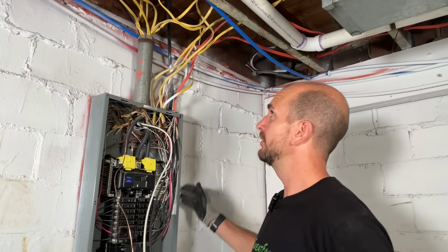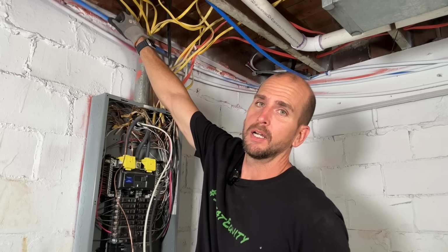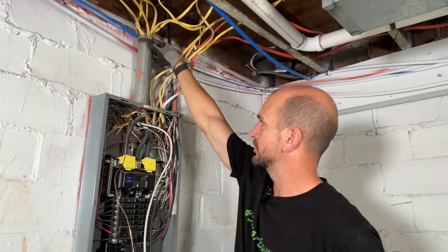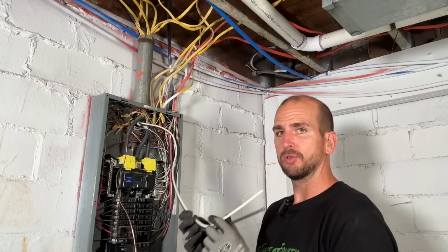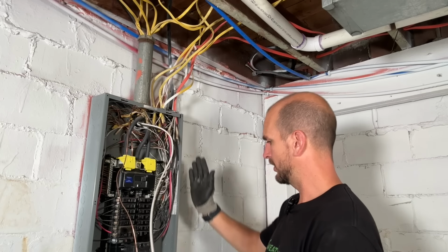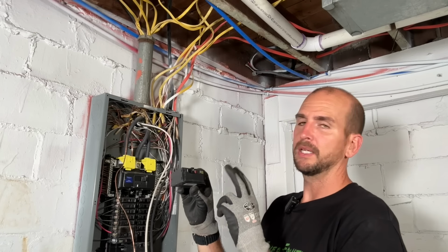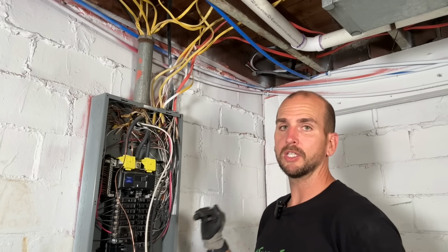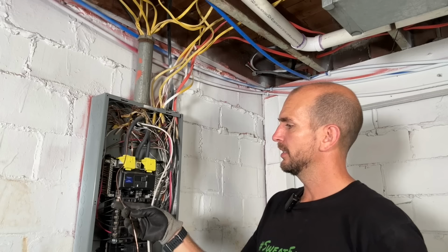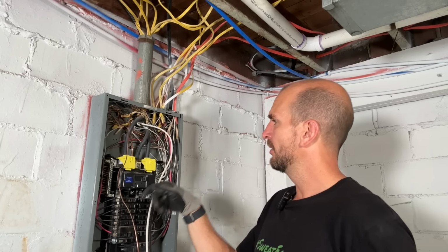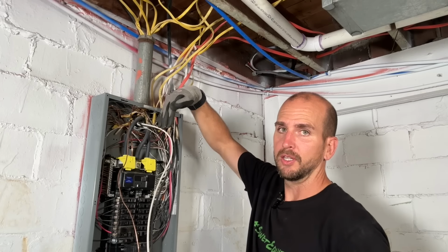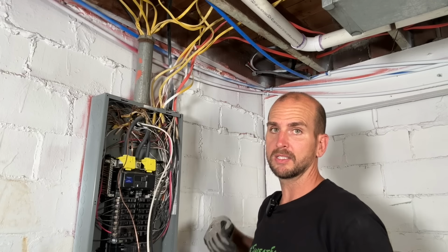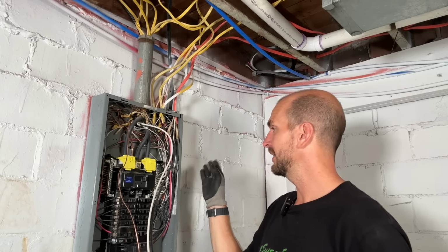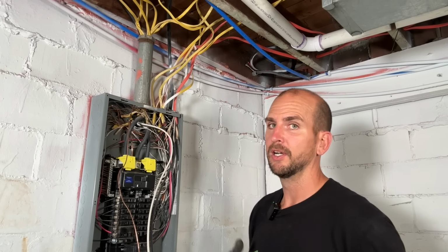So at the panel, I have my new Romex up top coming through the large central conduit. I have my two 6-gauge conductors that I'll run to this side, where I will then be installing a 50 amp Square D QO breaker on the right hand side. Then I'll land my 10-gauge ground. Right now this panel has all the grounds on the left hand side, all the neutrals on the right hand side. Now this is a main panel, so I can go to either side because the neutral and the ground are actually bonded together. So I don't need to keep them separated like you do with a sub panel.